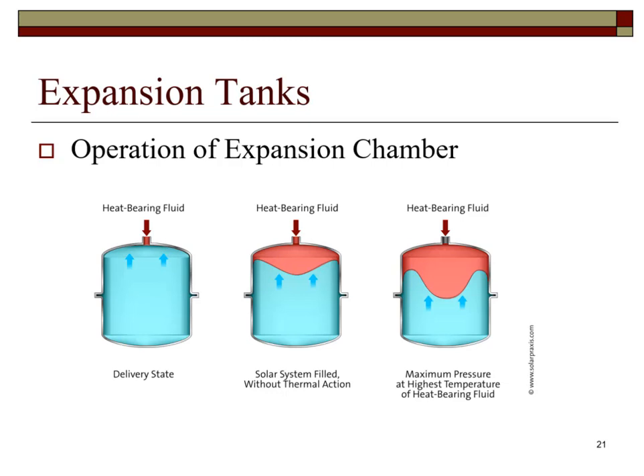The main function of the expansion vessel is to absorb the variation in the operating fluid volume during the changes in its temperature. The minimal expansion volume will be the total volume of the solar collectors and will vary on the use of the installation. It is convenient to take into account the vapor generation due to stagnation when sizing the expansion vessel.